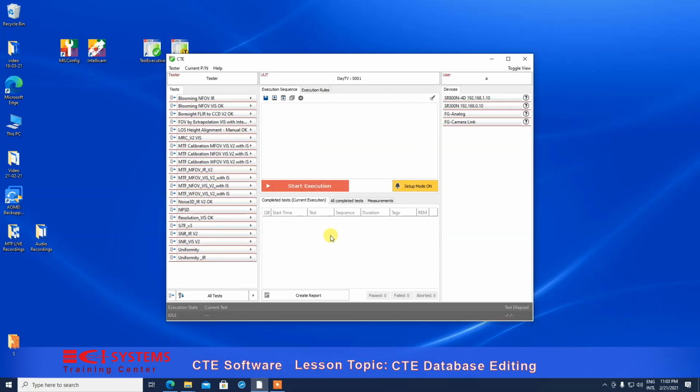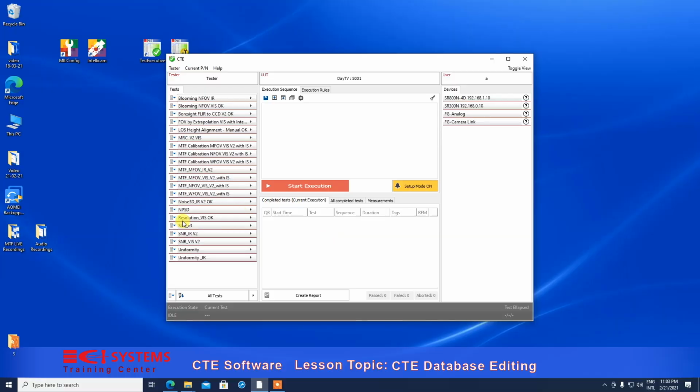So in this case, we're deleting all the IR tests basically from the day camera, because obviously you don't need them. But there may be other mixtures of tests that different cameras have. Maybe one camera has 3 fields of view, so I can delete 2 fields of view, which are basically the same test but different settings, like an MTF wide, narrow, or even super narrow, etc.